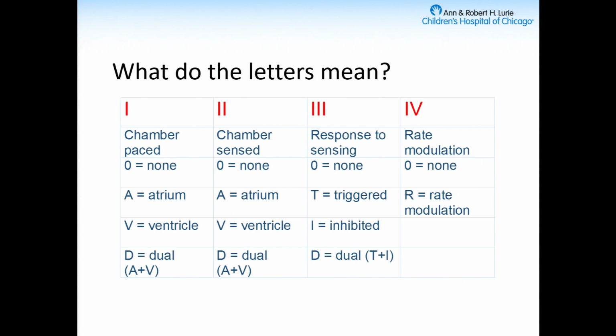The next one is about what's sensed. So if there's a 0 or an O there, that means that you're not going to sense anything. And we'll put patients into a mode where they don't sense, sometimes if they're going to the operating room and are going to have Bovie, because that can trick the device into thinking there's electrical activity in the heart that isn't actually happening. And so patients will not pace when they need to pace. So if you put them in a mode where it ignores electrical activity, you can allow your patient to continue to pace through an operation. And then obviously A is atrium, V is ventricle, and dual is both.